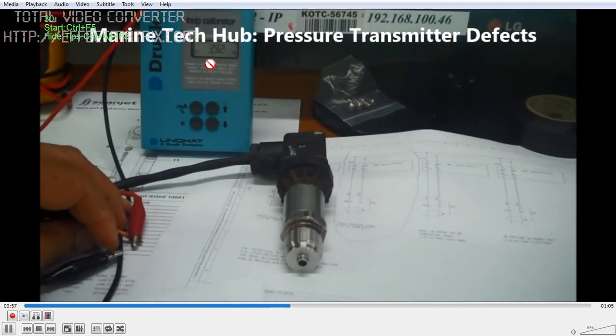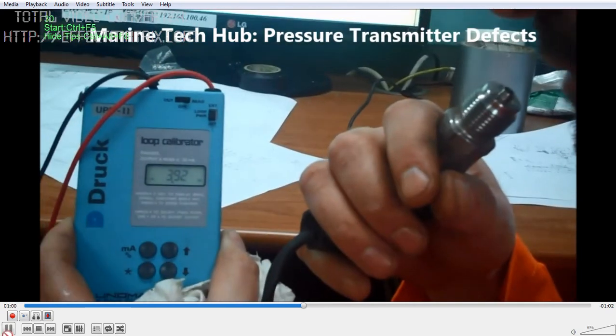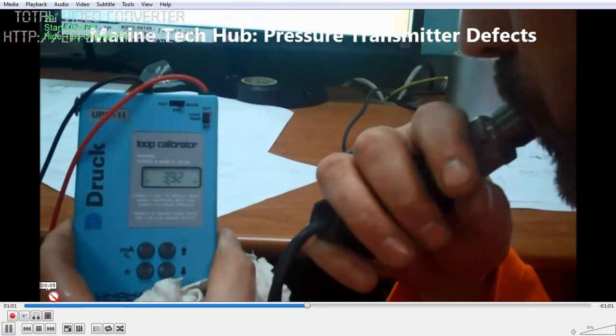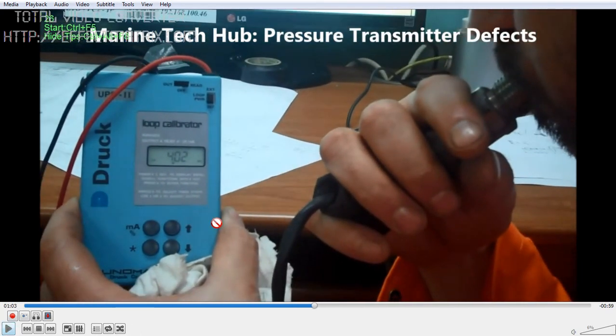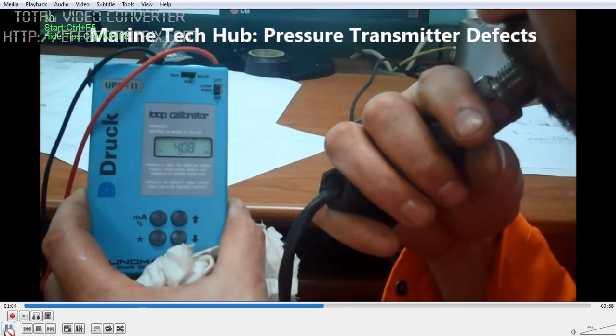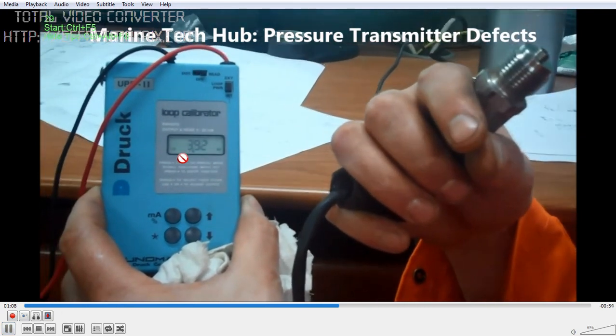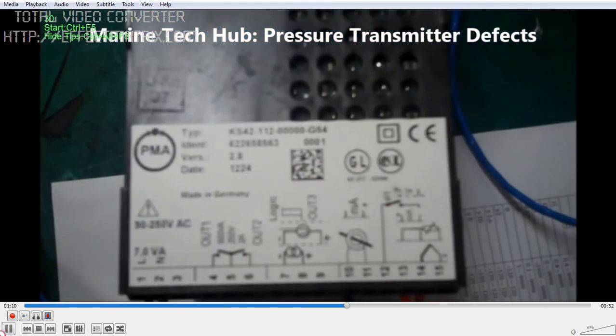To make sure it is working, I will just blow air by mouth into the transmitter. You can see the milliamps will increase — the reading should go up here. If it is increasing, that means the pressure transmitter is working alright. You can see the reading is going up, and when I remove my mouth the reading comes down. So the transmitter is confirmed okay.